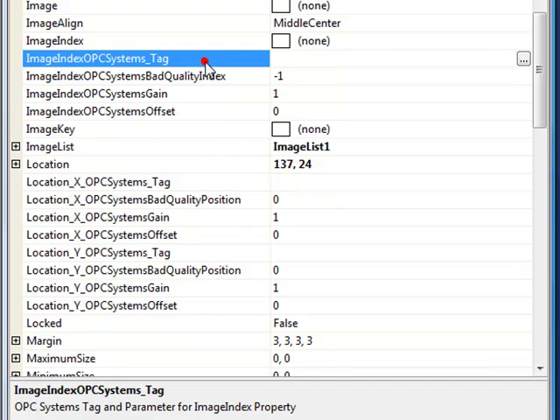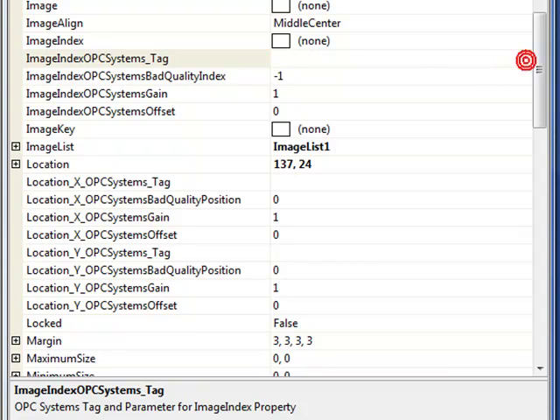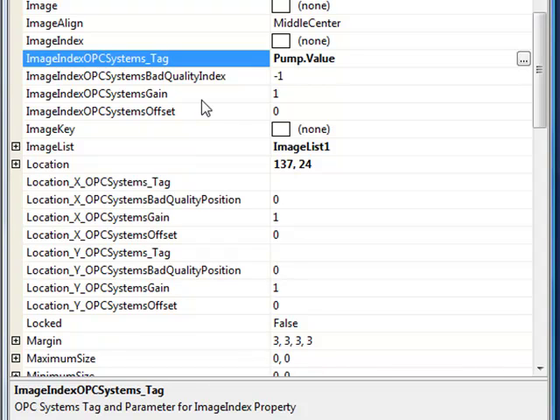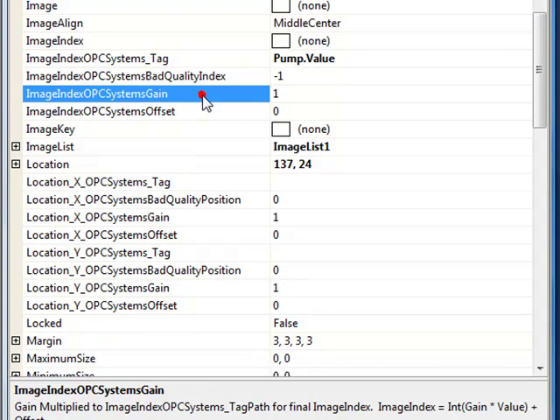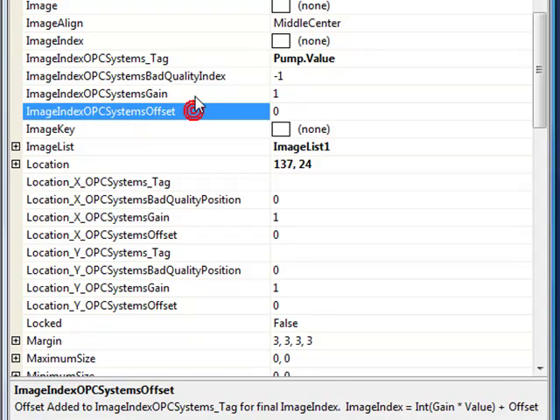We are now ready to define the image index opcsystems underscore tag property. And we will browse for that local pump signal. Now when the pump is off, we will display the first image of index 0. When the pump is on, we will display the second image of index 1.